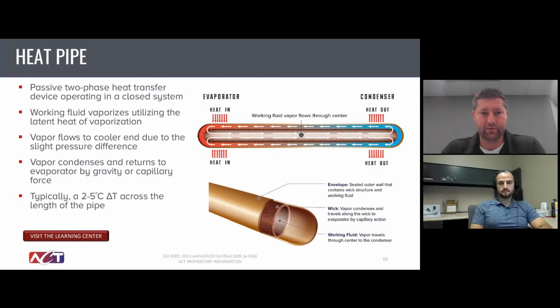This has been utilized for many years, and I'm guessing a number of the audience is familiar with this technology, but it's an extremely effective heat transfer mechanism. How it works is you have an evaporator, which, shown in this picture, is one end of the pipe, but it doesn't need to be an end of the pipe. It could be anywhere that you're introducing heat along the length. At the evaporator, that's where you'll couple it with your heat source. It'll take in that heat, vaporize the working fluid, and that heat source will create a pressure and temperature gradient within the pipe that'll push the fluid vapor to wherever it's colder in your system. In this example, that's the opposite end, which would typically be coupled to a heat sink.